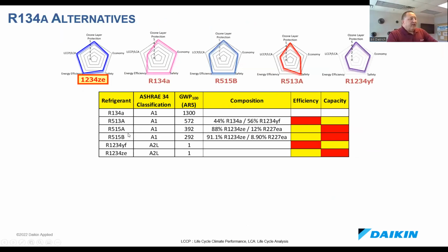So if we focus in on the 134A alternatives, you can see here's 134A, its classification, and its GWP based on the fifth assessment. Ideally, if you're going to a different refrigerant, you'd like a green here, you'd like more efficiency, more capacity. We're not really getting that with 134A. The closest we can get on efficiency is about the same with ZE, but you've still got a capacity issue. And then 515B, this is 91% ZE. What they did is add 8.9% of another refrigerant to move it from a 2L category to an A1. The impact is the GWP goes from 1 up to 292, but you can still get a fairly low GWP, less than 300, with a non-flammable refrigerant.